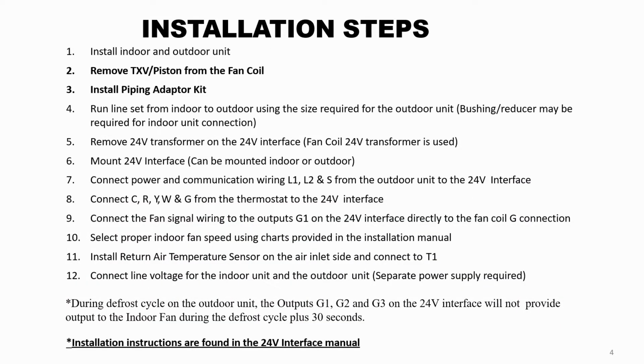The first step that's required is to mount the indoor and outdoor unit in their installation location, following the clearances required in the installation manual. The next step, and one of the most important, is to remove the metering device from the indoor unit, whether it's a TXV or piston. This may be easier to do at your shop as opposed to on the job or once the equipment's already mounted, but that's all going to be dependent on the specific job.